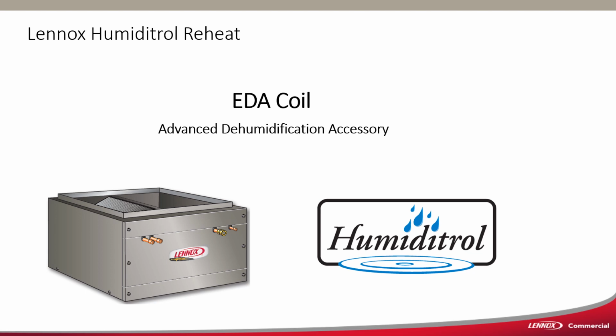We do also have the Lennox Humiditrol reheat system, or what we call the EDA, Advanced Dehumidification Accessory. This is very similar to the commercial package units reheat. The difference is this isn't hot gas, this is hot liquid. And by doing that, we do not have to pipe in a hot gas line from the condenser to the evaporator, which means as the installing contractor, you don't have to put in a liquid line, suction line, and hot gas line. This device mounts on the leaving air side of your evaporator coil, and we take the hot liquid right there from the expansion valve.